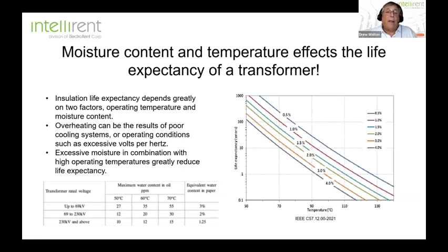So we know the life expectancy. This chart on the side of your screen is called the Lundgaard chart, and that's part of IEEE C57.12. Basically, this shows the life expectancy of the transformer based on temperature, and the life expectancy based on moisture content in percentage. That's percentage in the insulating paper. So you can see that the hotter the temperature and the greater the moisture content, the more dramatic the effect on the life expectancy of the insulating system.